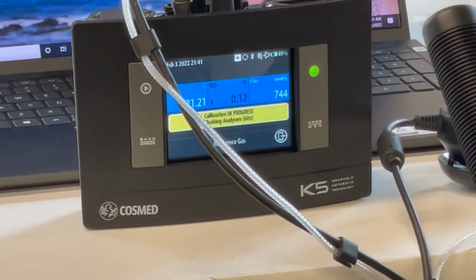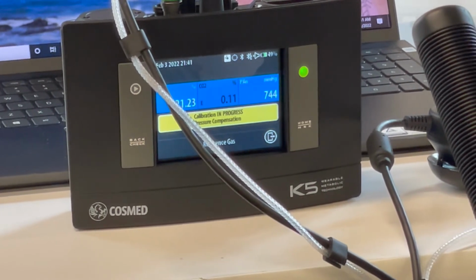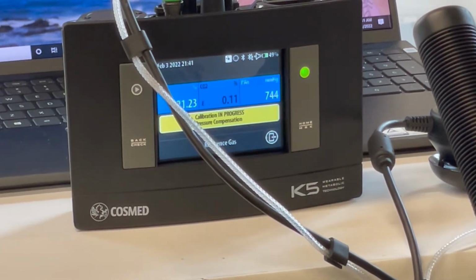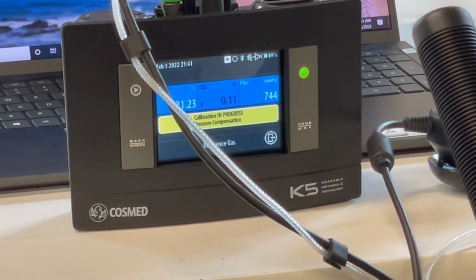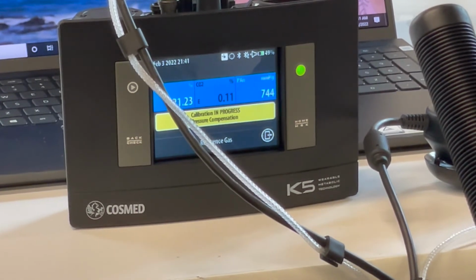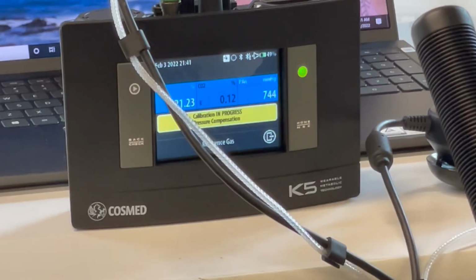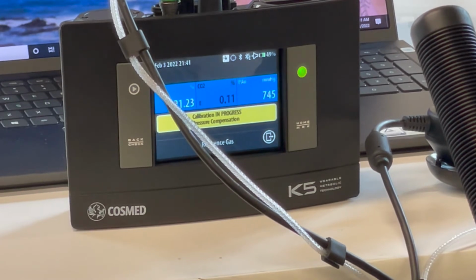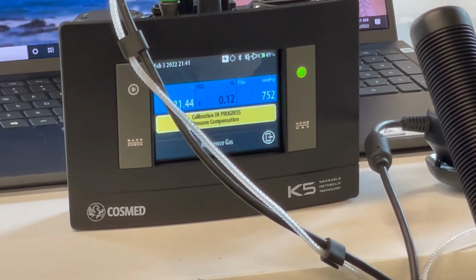What happens if you fail a calibration? Restart? Yeah, you'd want to rerun it and just double check, make sure that you have gas, make sure the sampling line is within spec, make sure the O2 analyzer is within spec, just double check all your stuff. And if it fails twice in a row, then just call me. Got it.